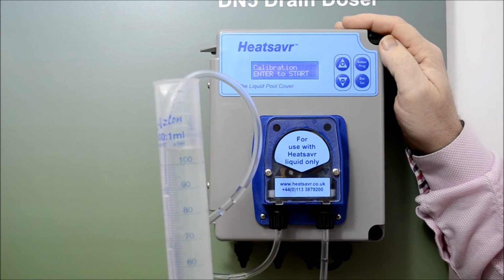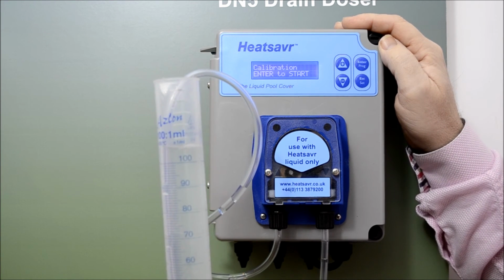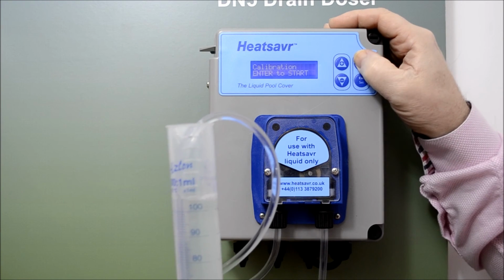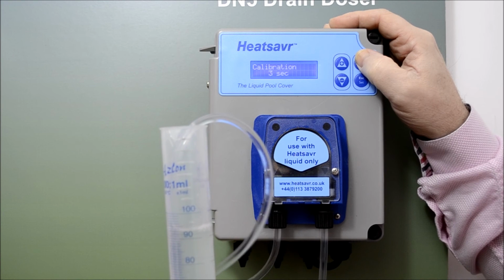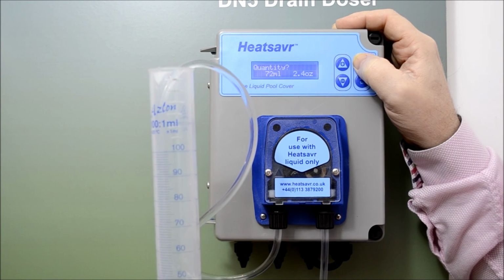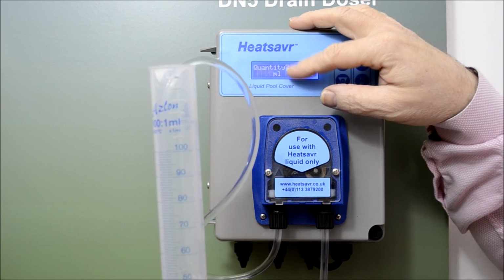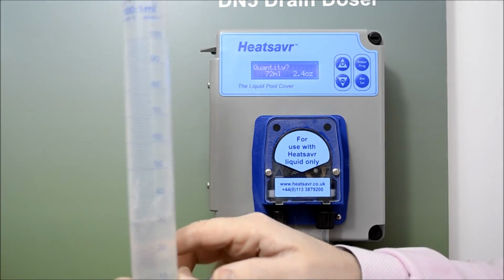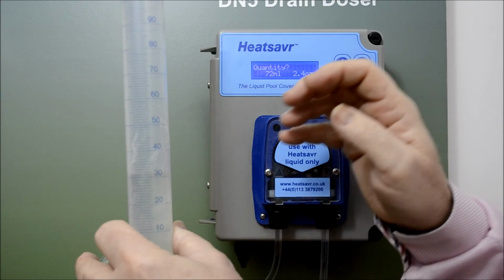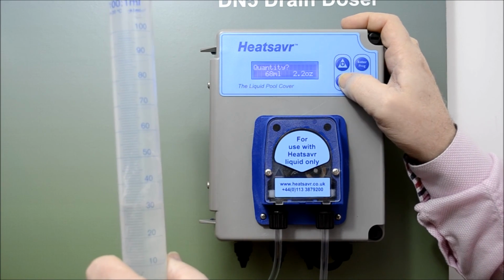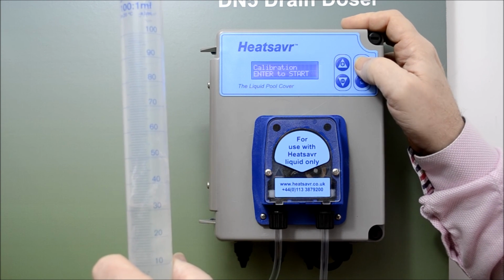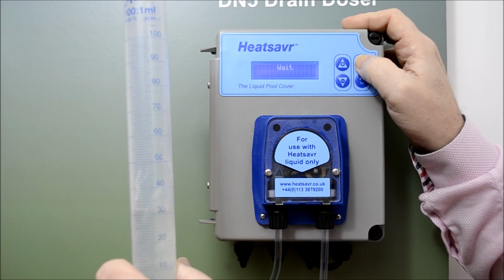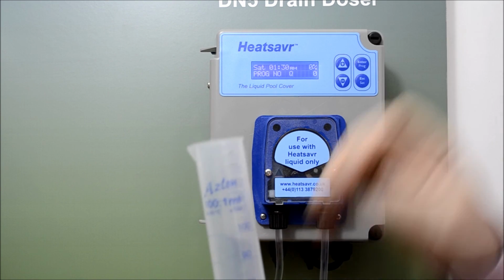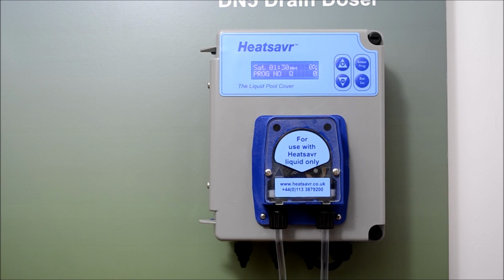On the screen a clock will then count up. 20 seconds is usually sufficient to give accurate calibration. Press enter to stop the calibration and then the estimated usage appears. Correct this using the up or down arrow buttons and enter to confirm. Then press the escape, then enter to save changes. The suction line can then be inserted into the chemical container. Press enter one more time and the screen will revert to the default display.